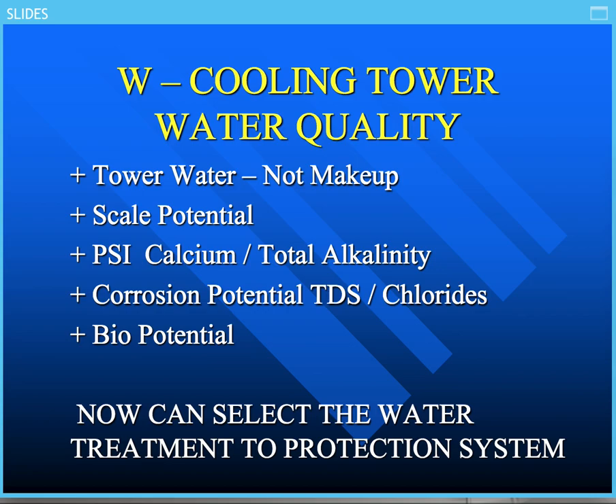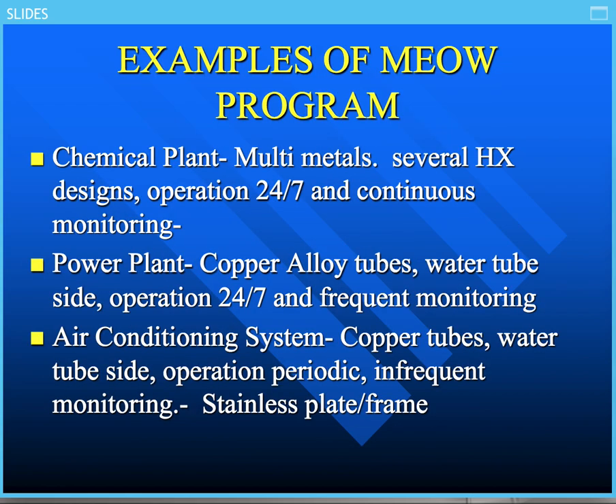So there's a lot of things that you have to look at to say, okay, let's make sure we have good biological control, whether it's using oxidizing biocide along with non-oxidizing biocide or just only an oxidizing biocide. And then we'll be talking a little bit about what we're dealing with. But now you can see what you need to know about your system. The MEOW program says, here's what you have to find out. Now you can actually select the water treatment program to protect your system. So let's take a look-see at a couple examples, or real quick ones.